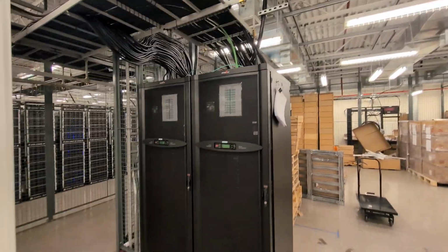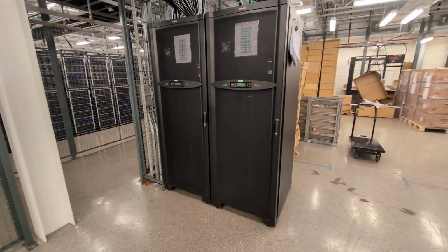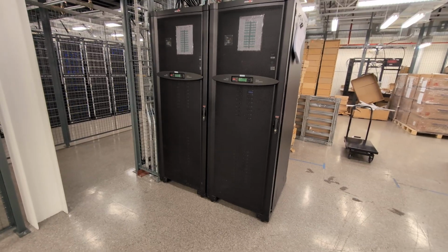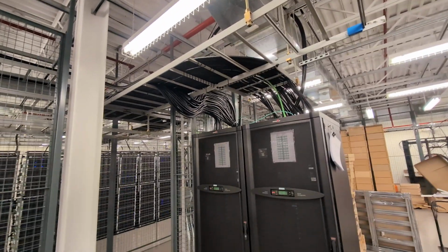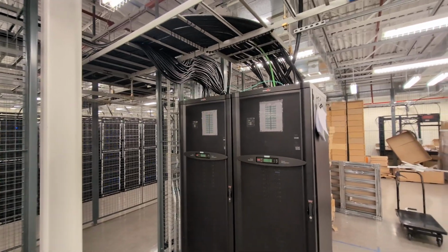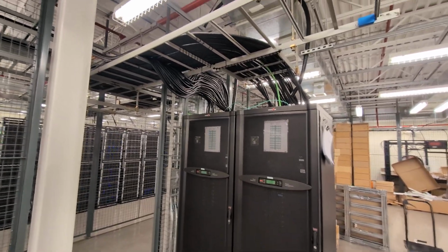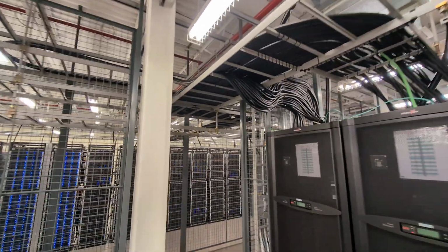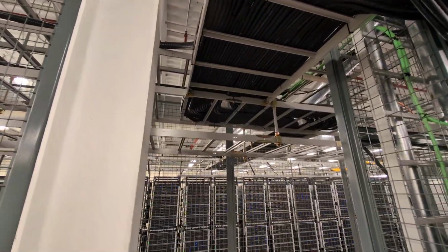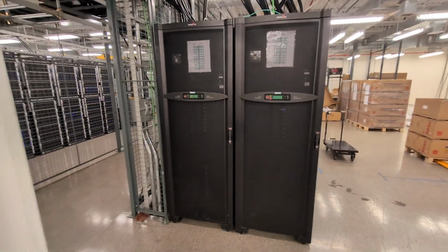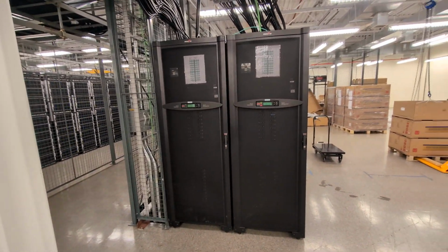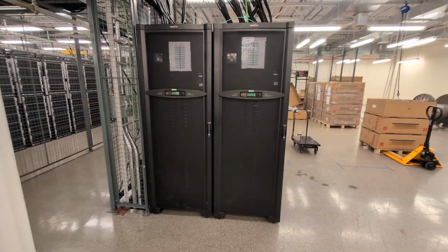Alright, these are our main power distribution systems right now. We have 250 kVA APC units, and each one of them is feeding one of those rows. Currently only one of these is fully active, the other one's just getting started. And that's how all the cables are distributed. So far this has worked really nicely. I'm imagining we're going to need at least 2 more of these, probably 2 to 4 more, to do the distribution for the full outlay of servers that we want.